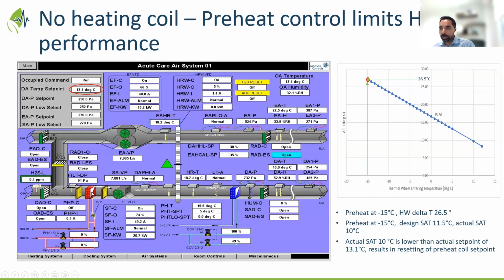So in order to meet that, what they had to do is increase the preheat set point, because there is no other way for them to add heat to the system in this current configuration. So they had to increase the preheat set point, which, as you see from this graph, means your entering air temperature to the wheel is going to increase, which means your delta T is going to decrease across the wheel. So you're indirectly underusing the wheel by increasing the preheat set point.